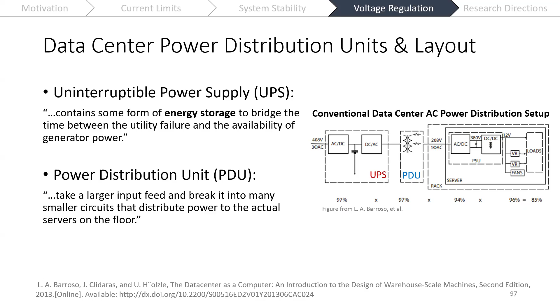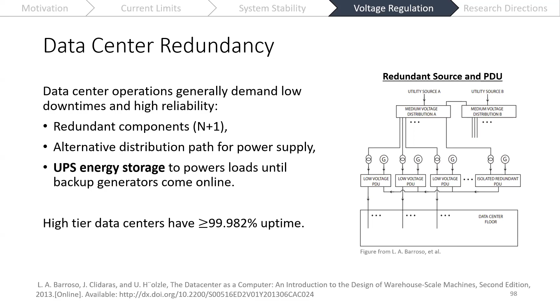Data centers need to maintain a certain level of redundancy, at least to get certain kinds of high value customers. So what they usually have is lots of redundant components and alternate paths, even potentially different connections at different points in the utility system. But in addition to this, they also usually have additional UPSs and a good amount of energy storage available to make sure that if something happens, even in the case where one of these uninterruptible power supplies goes offline, we're going to have enough energy to satisfy our load until a backup generator comes online.